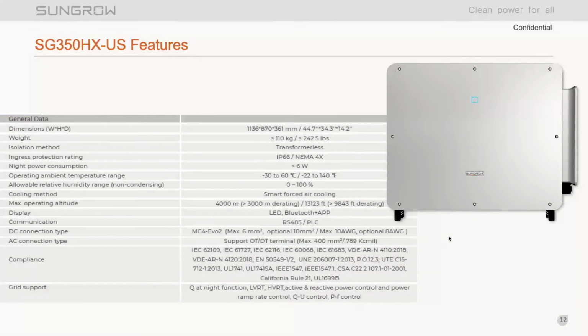I'm not going to go over every single one of these features of the general data, but the weight is 242.5 pounds. It's really not that much heavier than the SG250 was. So from a power capacity versus weight ratio, this is definitely top of the market. It is a NEMA 4X rated inverter, obviously, for outdoor installation, and the corrosion protection that we have on the SG350 is C5. So it is C5 rated as standard.